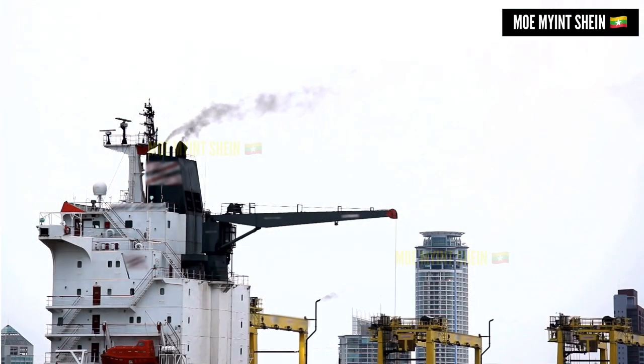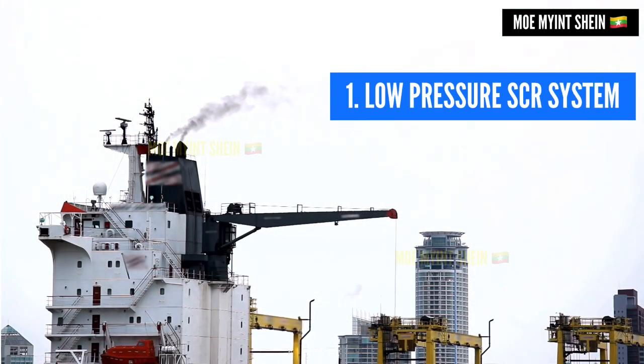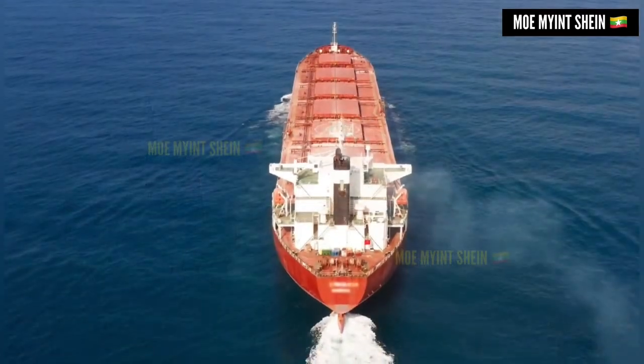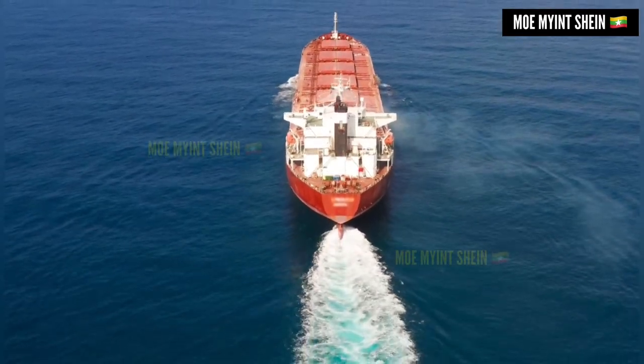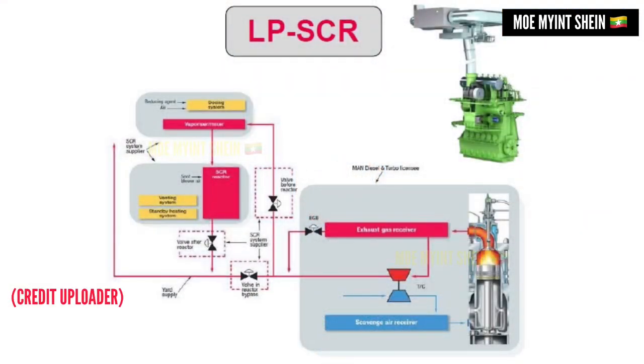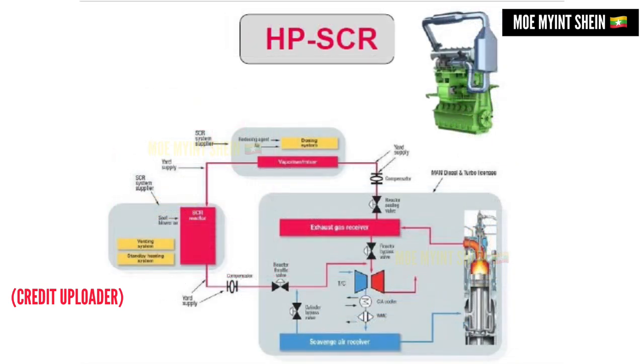There are two different types of SCR system: low pressure SCR system and high pressure SCR system. In a low pressure SCR system, the SCR reactor is placed after the turbocharger. However, the SCR reactor is placed before the turbocharger in a high pressure SCR system. High pressure SCR system is more compact than low pressure SCR system — it requires less space and shorter piping length.